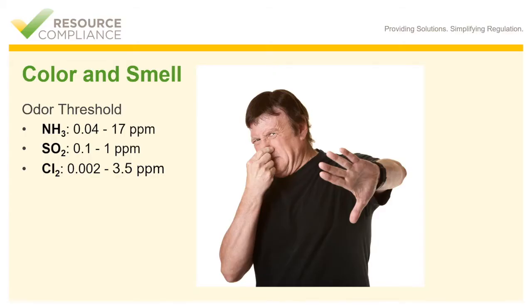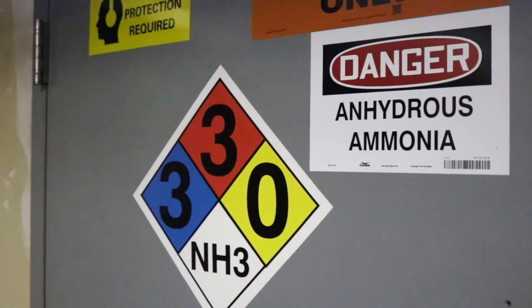Ammonia has a very low odor threshold. This is a great characteristic of ammonia — you could smell ammonia long before the concentration is harmful to your health. For example, you could smell ammonia around 5 parts per million, which is only one-fifth of the permissible exposure limit for ammonia in California. More on exposure limits to come.